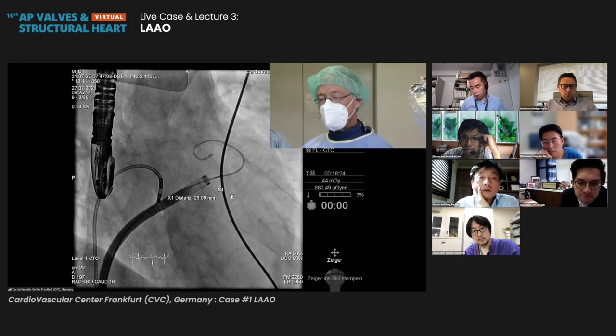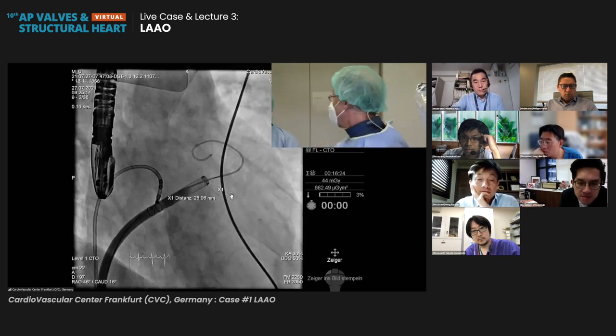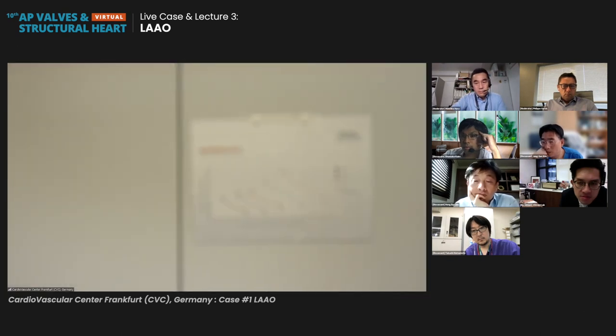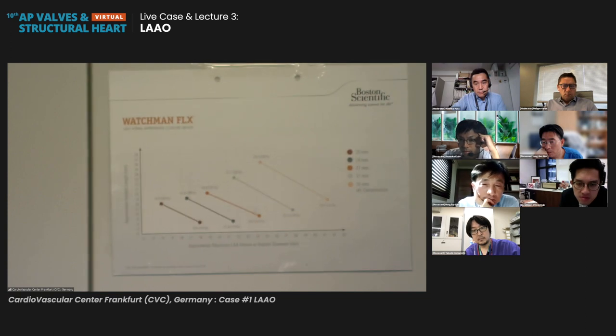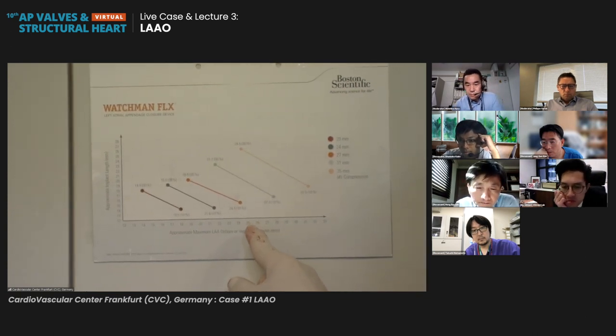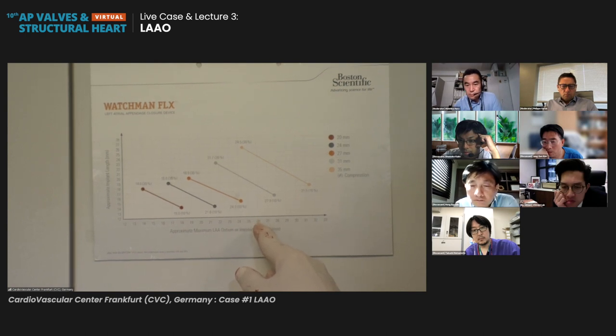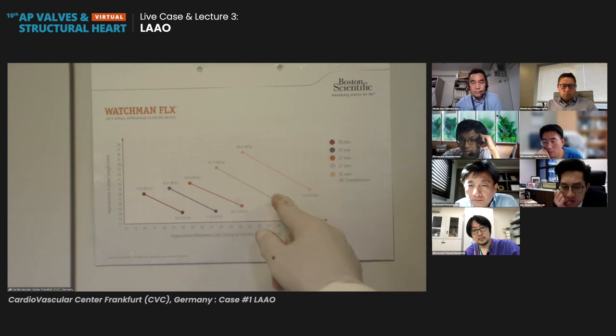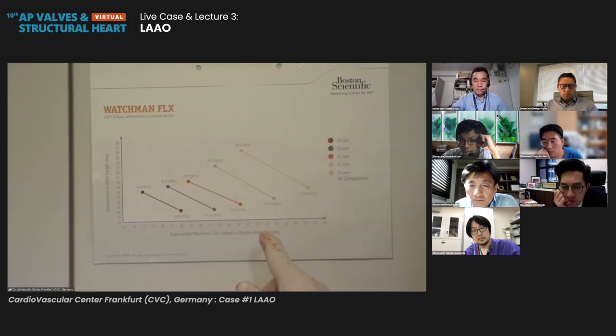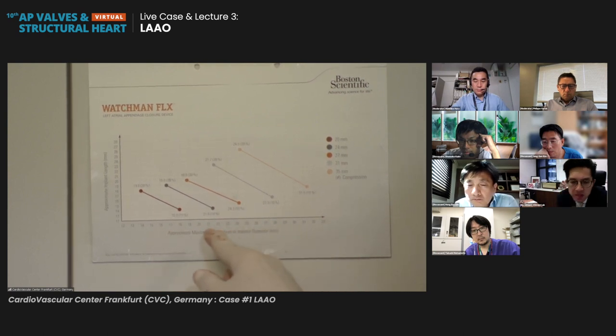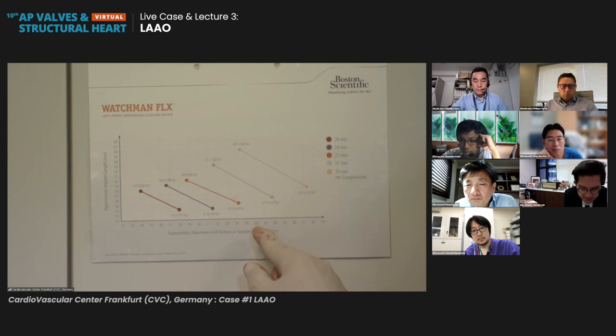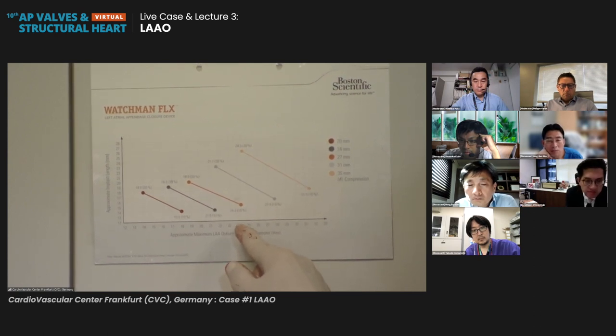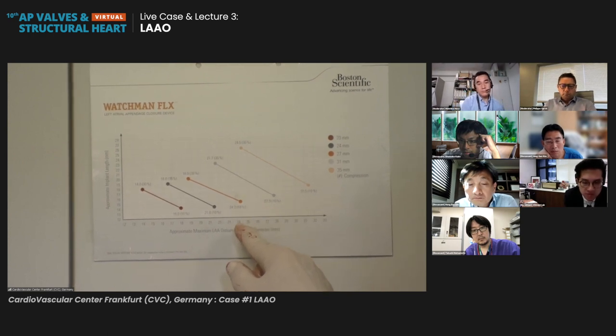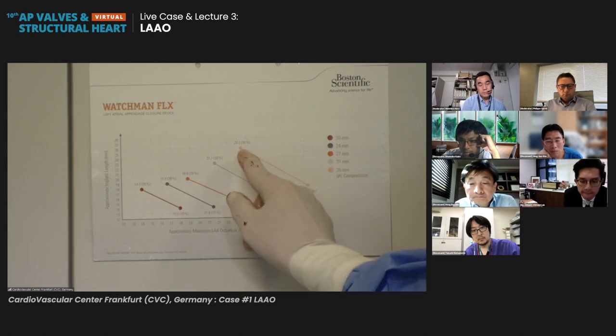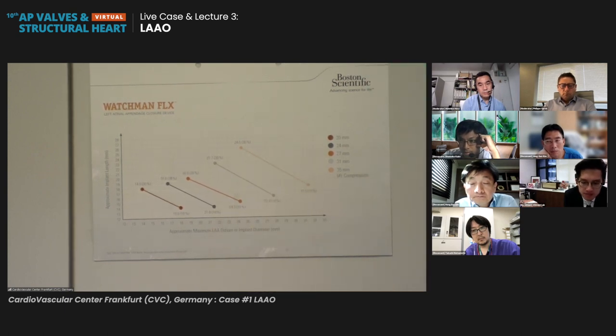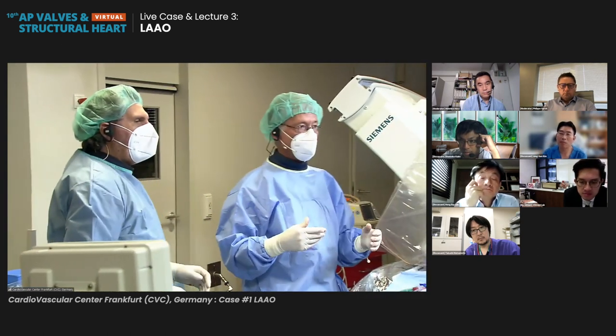So let's think about the size of the device we're going to use. Can we focus on the sizing chart? Okay, so if we say the diameter is about 25, 26, then this would indicate that we should use the 31 millimeter Watchman Flex. For those of you not familiar with the Watchman Flex, this is the landing zone, and you can see that, for example, with a 24 millimeter landing zone, we could use either the 27 or we could use the 31 and maybe also the 35, which means with the Watchman Flex, you have a much larger range of sizes you can cover with your devices.